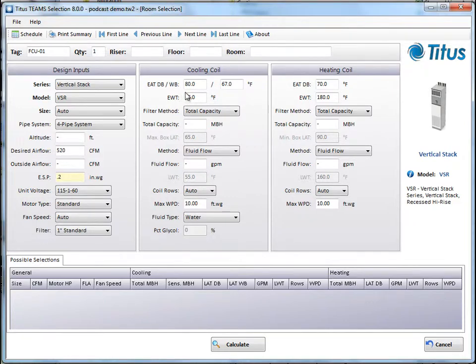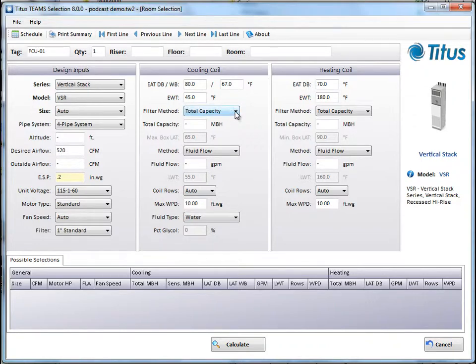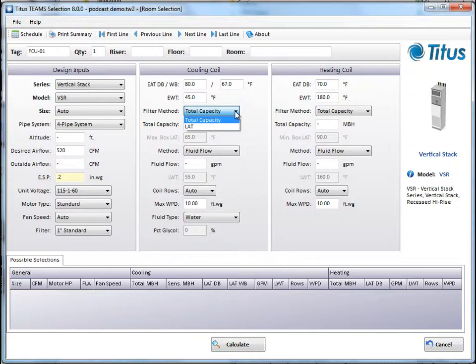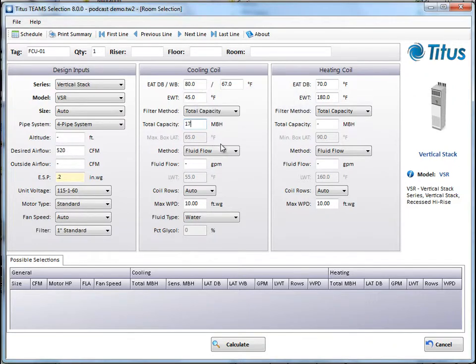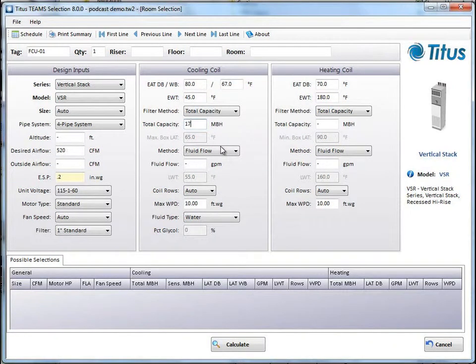Now we have the cooling coil and heating coil information. You can put in your entering air temperatures and your entering water temperature, and then there's two different methods to select. You can select by capacity, or you can select by leaving air temperature. We'll leave it on capacity, and let's put in here about 17 MBH.